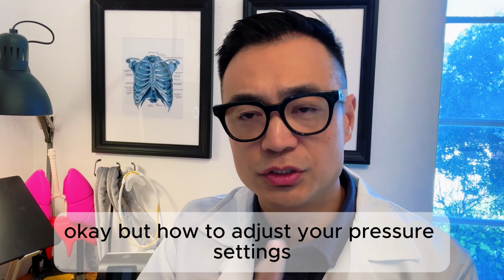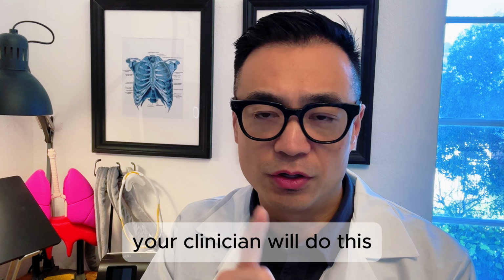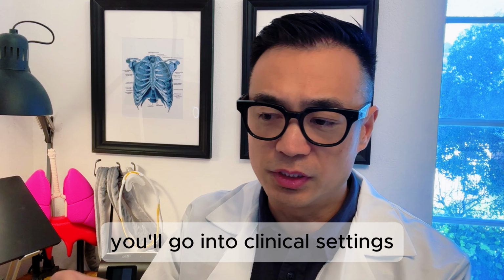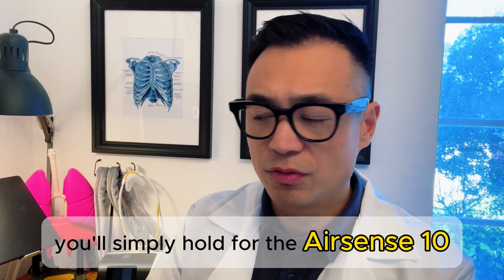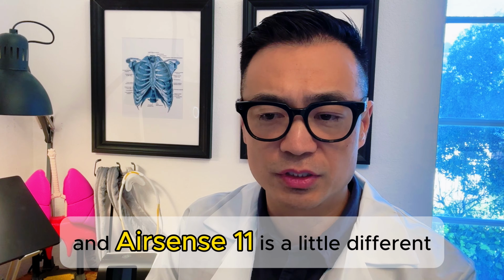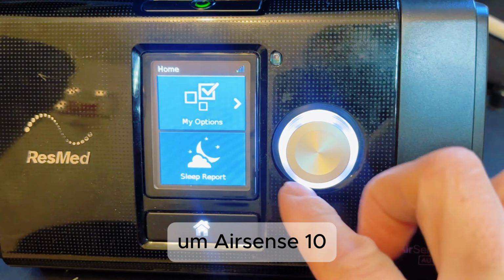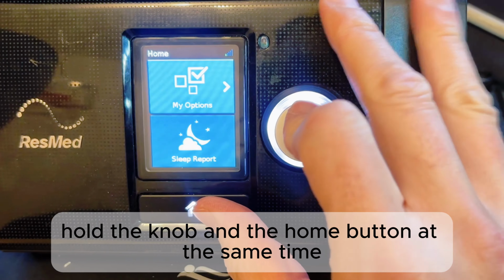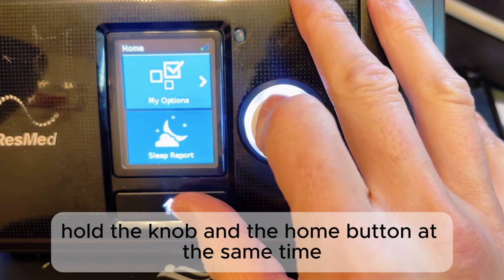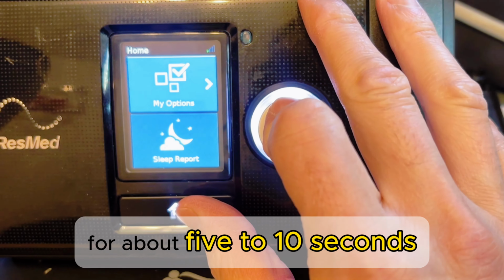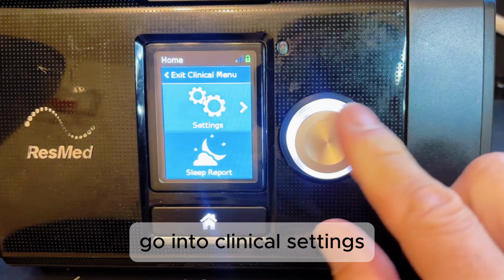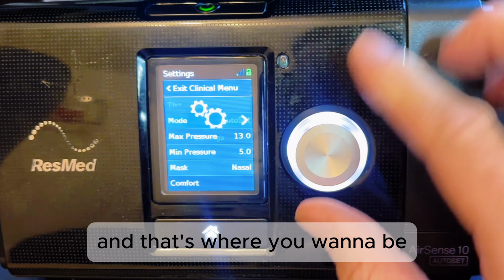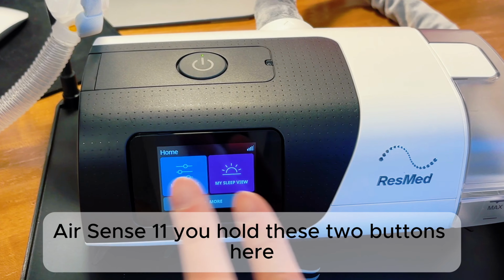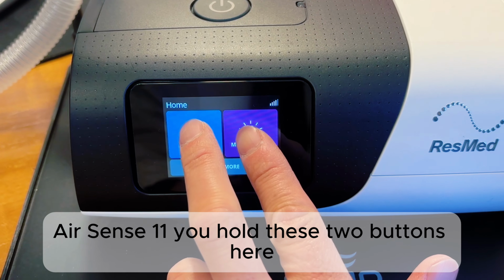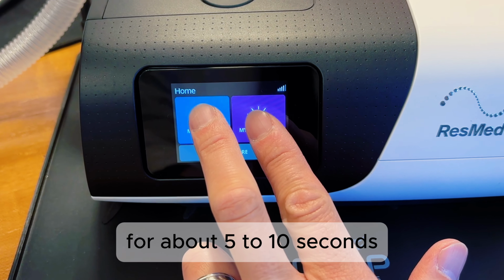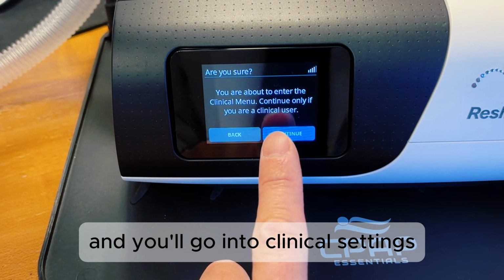But how to adjust your pressure settings? Your clinician will do this. You'll go into clinical settings. You'll simply hold, for the AirSense 10 and AirSense 11, it's a little different. AirSense 10, hold the knob and the home button at the same time for about 5 to 10 seconds. Go into clinical settings, and that's where you want to be. AirSense 11, you'll hold these 2 buttons here for about 5 to 10 seconds, and you'll go into clinical settings.